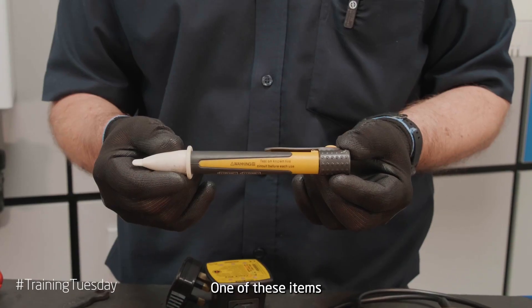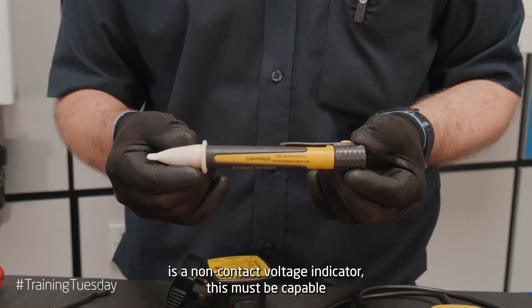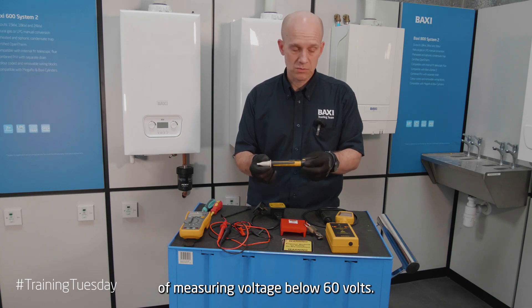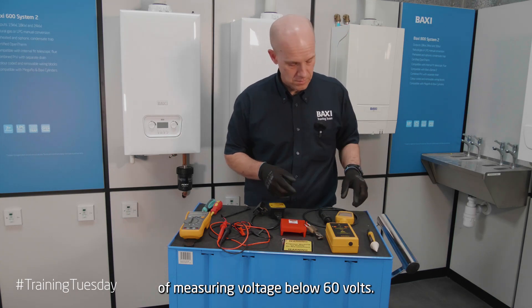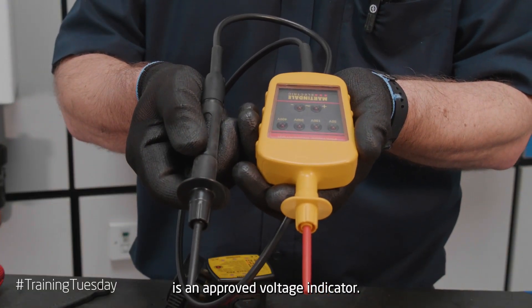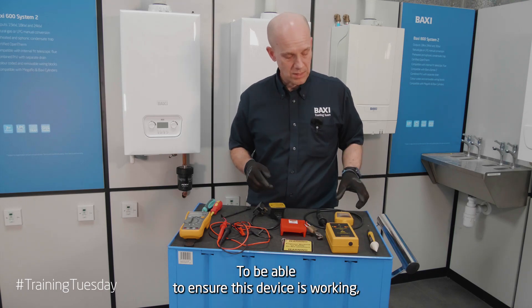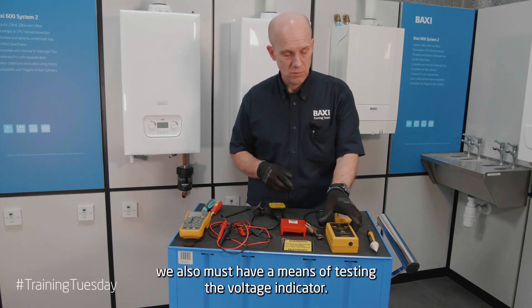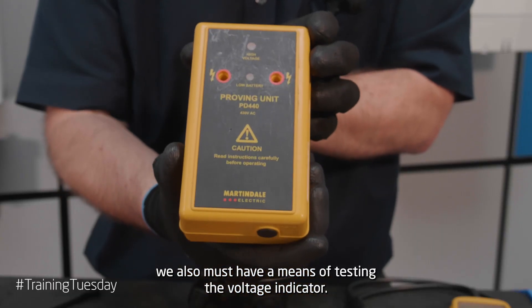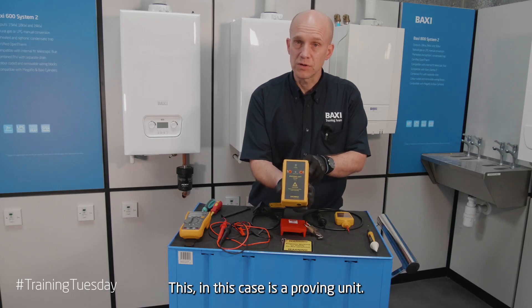One of these items is a non-contact voltage indicator. This must be capable of measuring voltage below 60 volts. The next item we need to be using is an approved voltage indicator. To be able to ensure this device is working, we also must have a means of testing the voltage indicator — in this case, a proving unit.